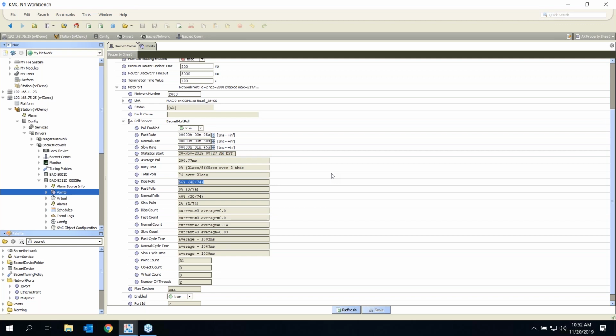So when a point first transitions into a subscribed state, it gets added into the Dibs stack, and it also gets put into its applicable queue. And Dibs has head of the line privileges. It interrupts the polling of the 3 queues, and we pop the stack off the top. So last in, first out. The most recent thing that's become subscribed is what gets popped off the Dibs stack first. We try to update that information first because that's the UI someone's looking at. And then once the Dibs stack is emptied, it resumes the normal polling of the things that are in the queue.